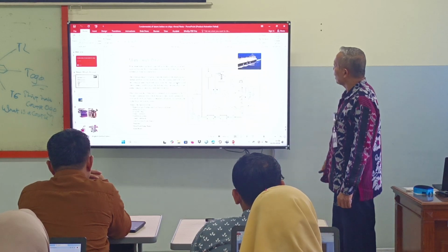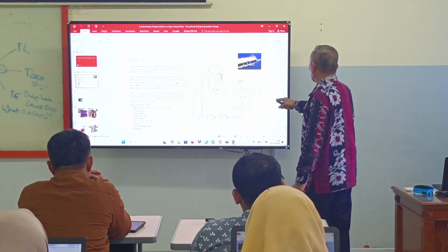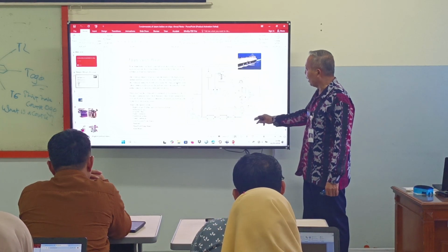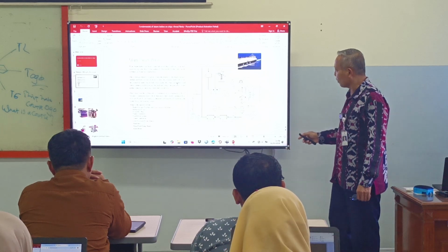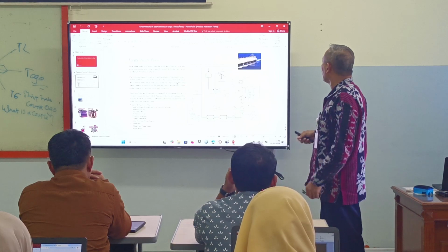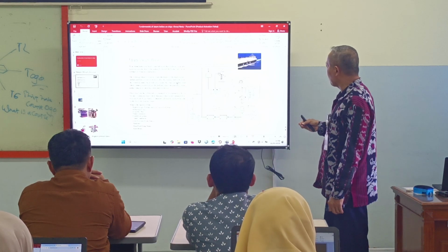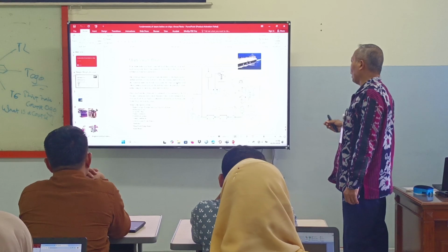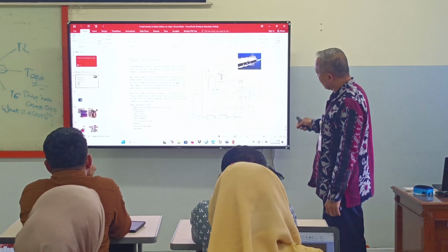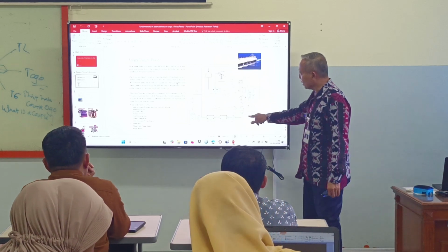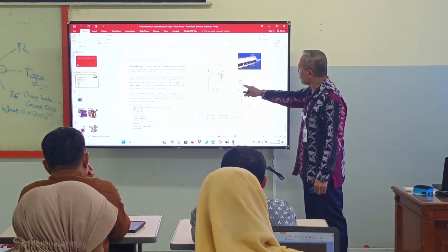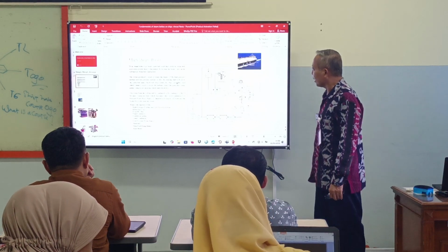The reduction gear turns the propeller, and makes the ship go ahead and astern, with the turbine astern. The low pressure turbine steam is turned to water in the condenser, the main condenser. What is the main condenser? The main condenser makes a vacuum of steam, cooled by seawater, and then the steam becomes fresh water. Green is for fresh water, red is high pressure, and yellow is low pressure.